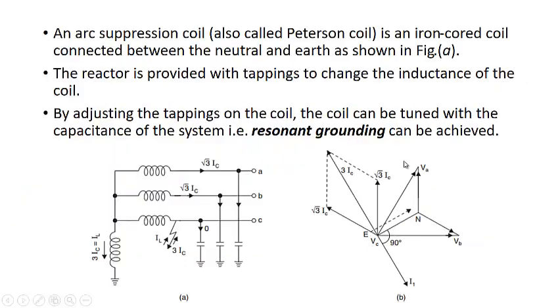So in this case, this arc suppression coil, which is also known as Peterson coil, is an iron core coil connected between neutral and earth, as shown in this. You can see from here. This is similar to an inductance, or you can say reactance grounding. Only thing, it has tappings over here. So the tappings are changed to exactly balance this current and this current.